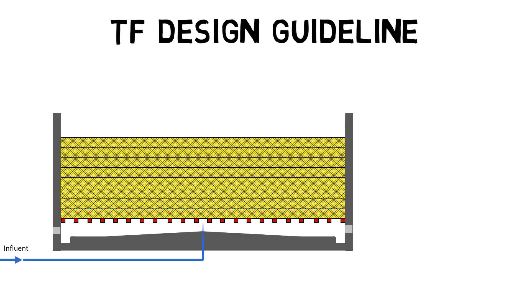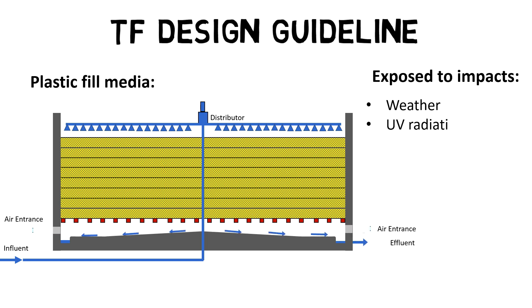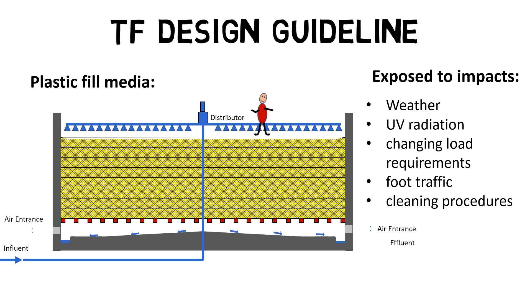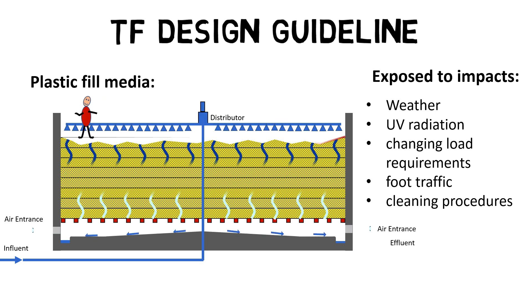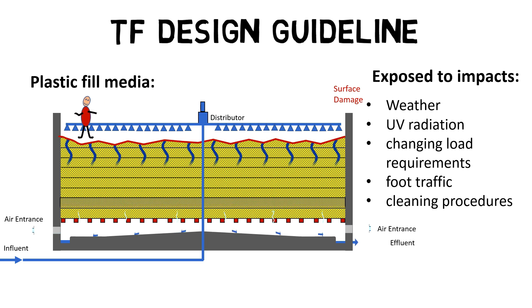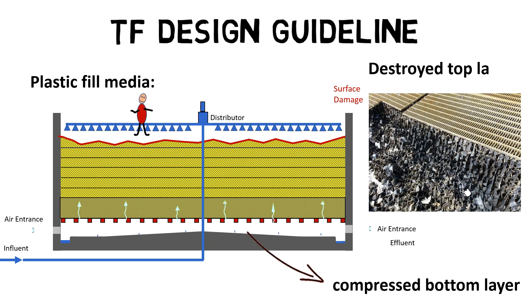During the lifetime of a trickling filter, the plastic-fill media will be exposed to many different outer impacts, such as weather, UV radiation, changing load requirements, foot traffic, and cleaning procedures. In the beginning, these effects will be barely noticeable, but over time especially the bottom and top layers of plastic-fill media start to deteriorate. With increasing damage, the air and water distribution within the trickling filter gets worse and worse, so that the performance starts to decrease. When the bottom layer compresses and the top layer shows cracks and broken channels, it's time to exchange the plastic-fill media.